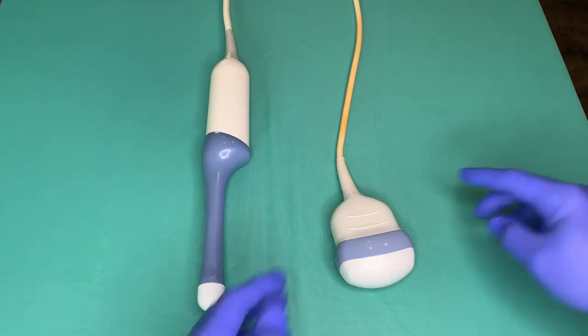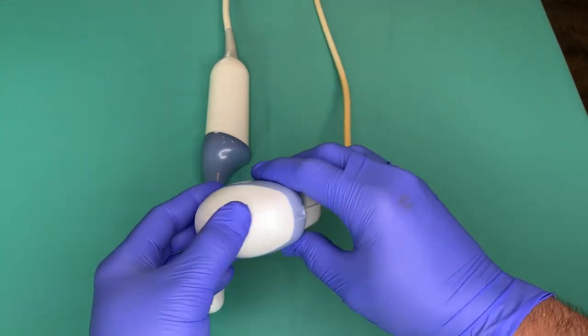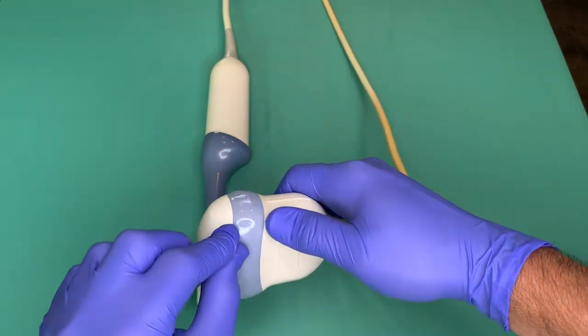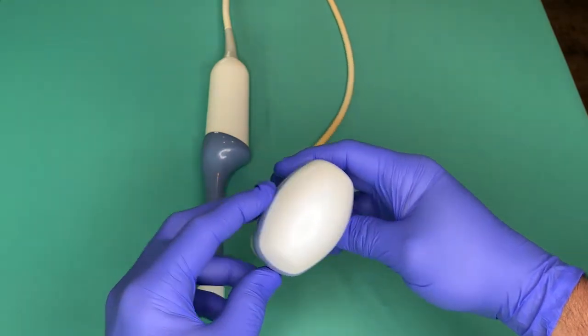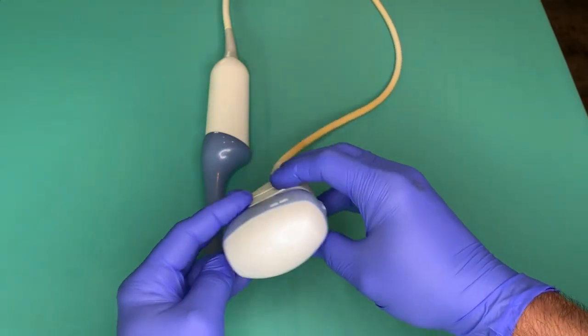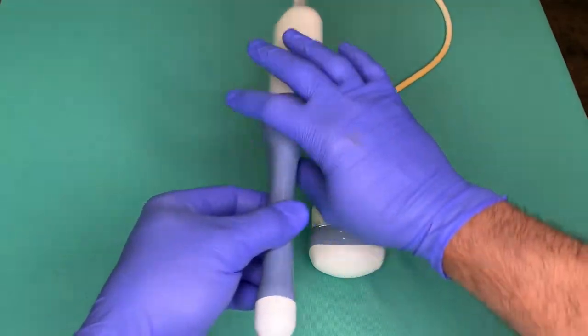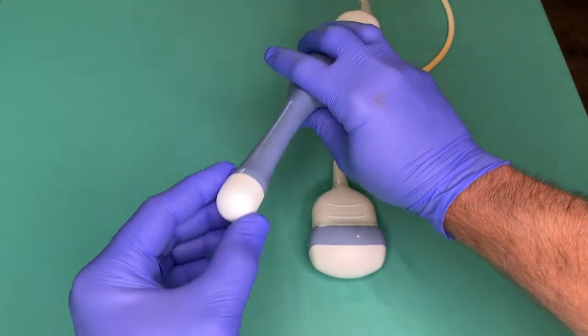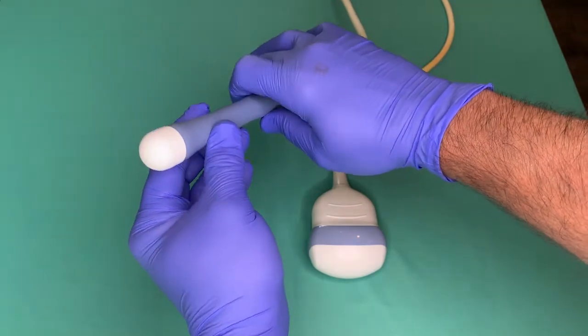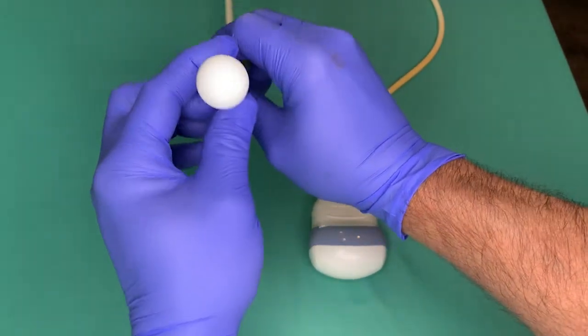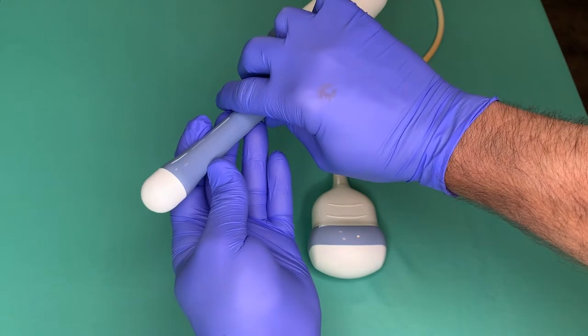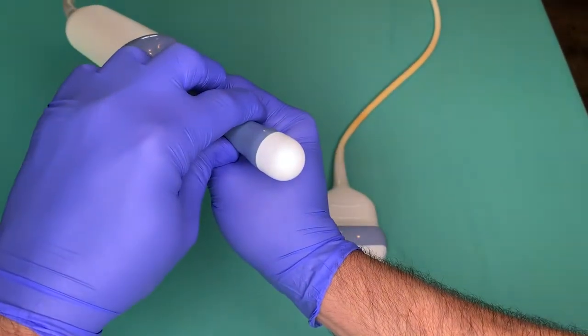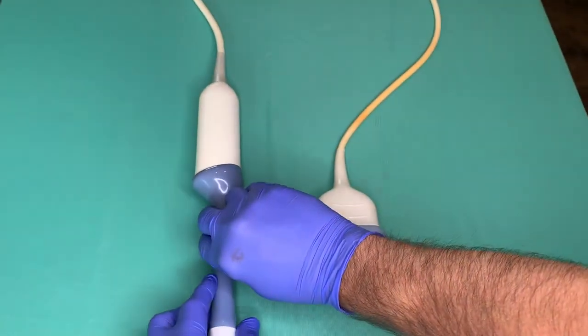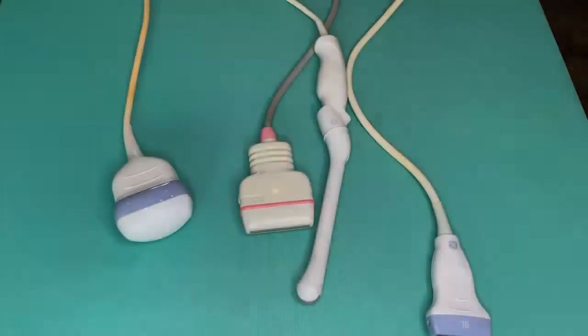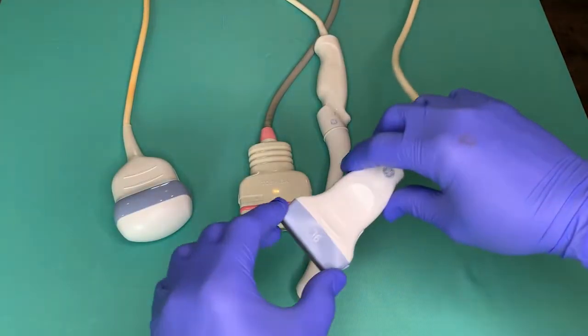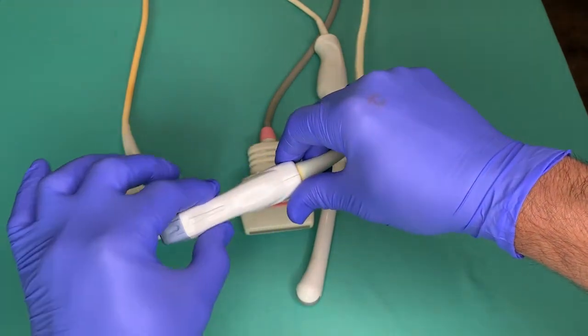The dome covers highly sensitive systems that mechanically oscillate the array during 3D imaging. The dome is attached to the upper probe housing with adhesive, and the entire area is filled with oil. The dome should appear smooth, with no visible bulges or areas where the underlying mechanics may be pressing against the inside of the dome. There should be no deep scratches or gouges on the surface of the dome, and no weeping of oil. The probe housing is a covering for the scan head and associated electronics and mechanics.